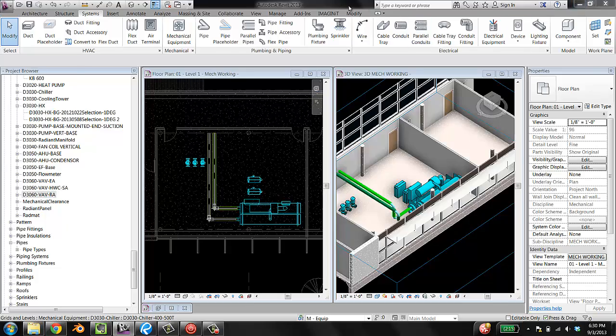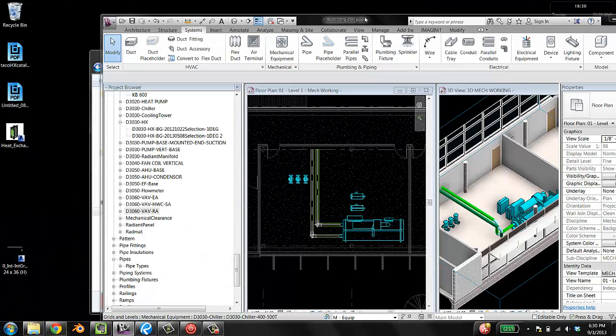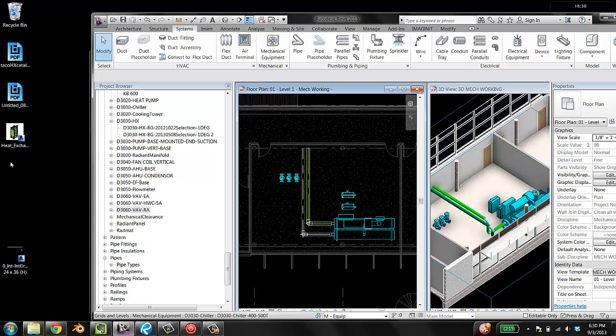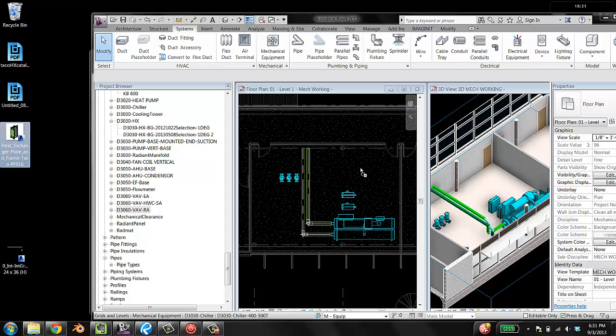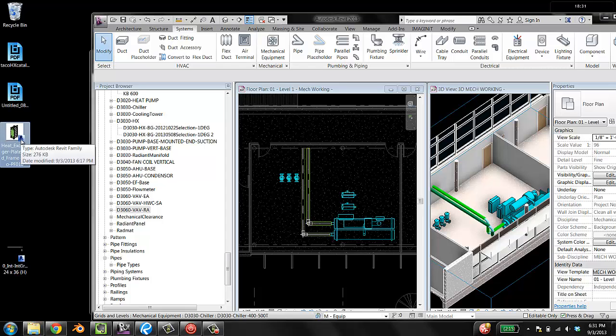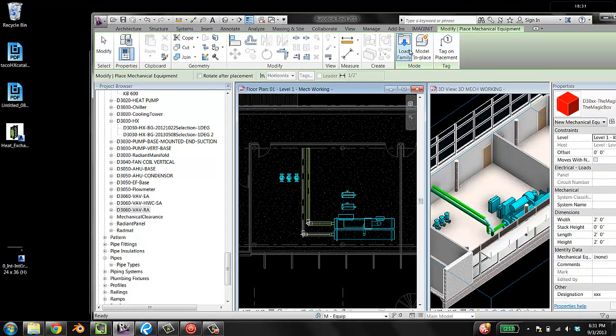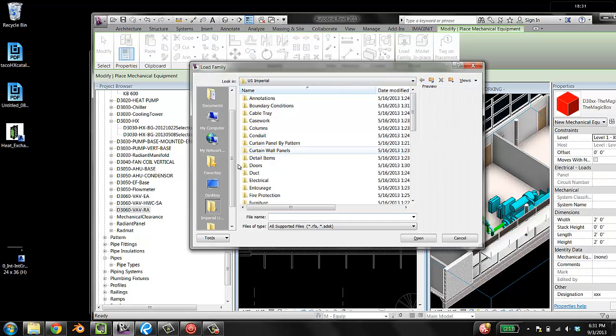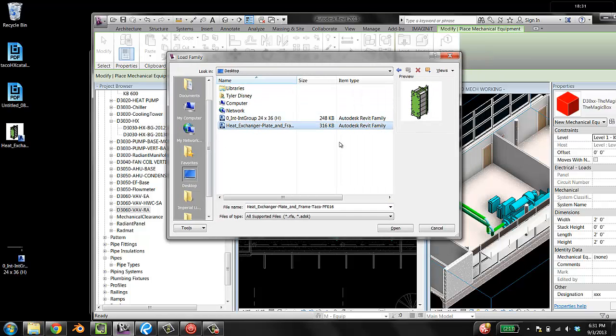It's technically possible to simply drag the family from your desktop into Revit, and it would be okay with this family. However, if your family had a corresponding text file, Revit wouldn't know that text file is there if you just drag and drop. There's a process that will allow Revit to recognize the text file: go to the Systems tab, Mechanical Equipment, Load Family, and then browse for the family. If you do this every time, you won't get yourself in trouble.